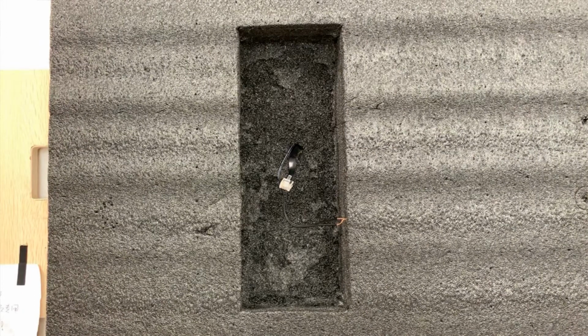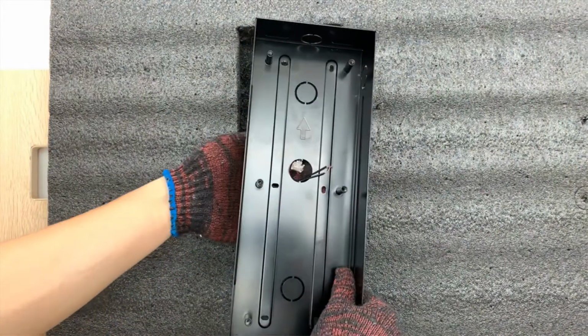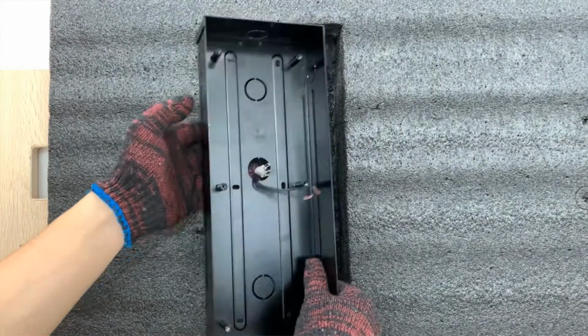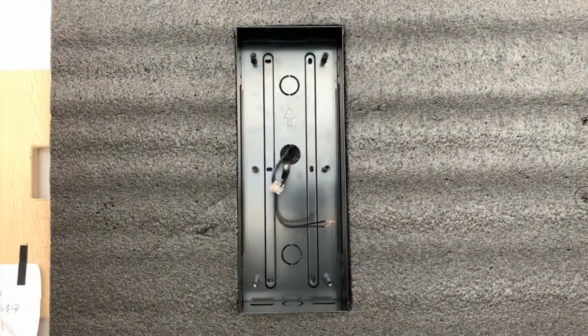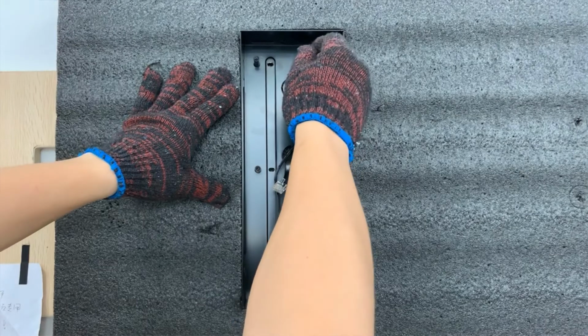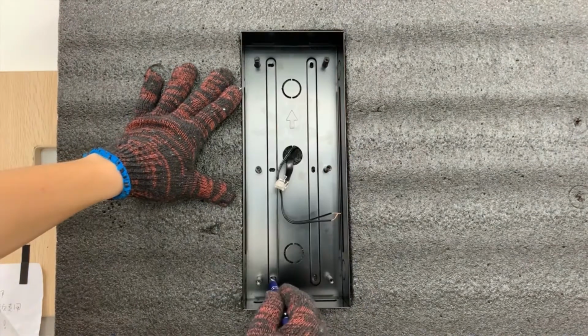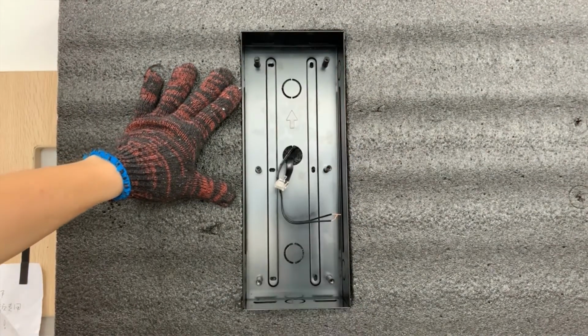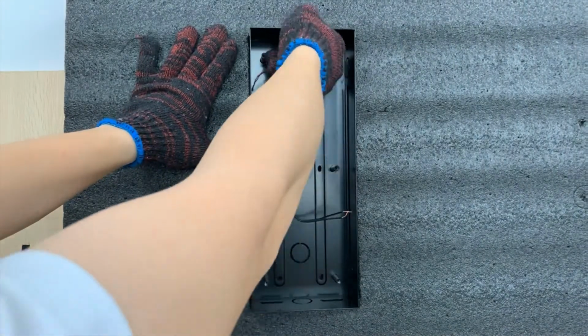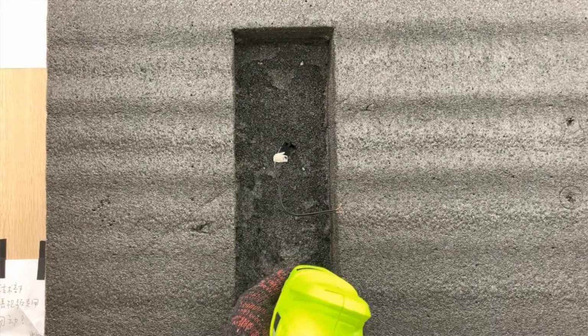As for the dimension of the square hole for the embedded box, please refer to the recommendation in the installation quick guide. Place the bracket properly on the wall according to the position of the hole. Then, use a pencil to mark the location of the holes on the wall. Use a 5mm diameter bit hand drill to drill the holes.